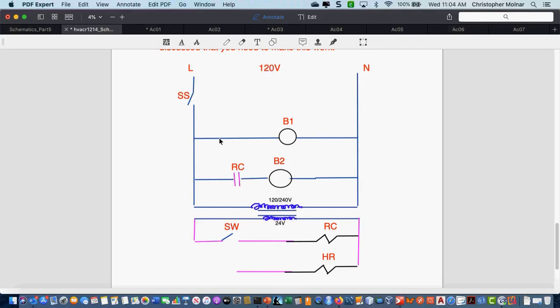Now, what do I have to do up here in line with bulb 1? What goes in here? Add the second contactor. Okay, another contact. I did hear someone say thermostat. Thermostat we're going to put on our low voltage side. Yeah, I just realized that the thermostat goes on the bottom. That would make sense to put it there. Okay, so I'm just going to copy that, and I'm going to throw it up there. Now, can I leave the designation RC on this one? No. Have to change it to match this, right? Have to change it to match the HR. This is why labeling becomes important, by the way.